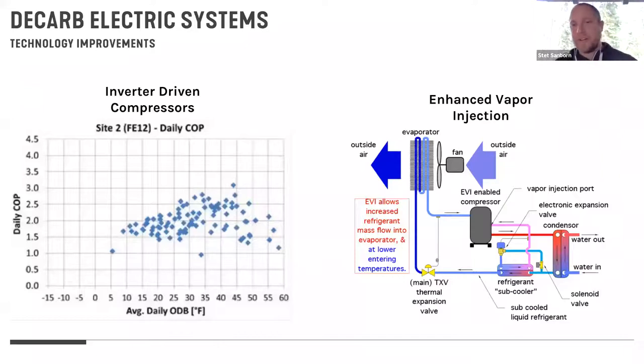I don't want to, well, actually this is ASHRAE. So I gave this talk earlier to architects when they all glazed over, but this is ASHRAE, so I can nerd out here a little bit. So what you see in enhanced vapor injection, for those of you who haven't used heat pumps that have it, is that as that hot refrigerant is coming off of our condenser coil, it's given up some of its heat, but it's still relatively warm. We can pull off a side track of refrigerant and pass it through an electronic expansion valve and heat exchanger to remove even more heat, or subcool that refrigerant.